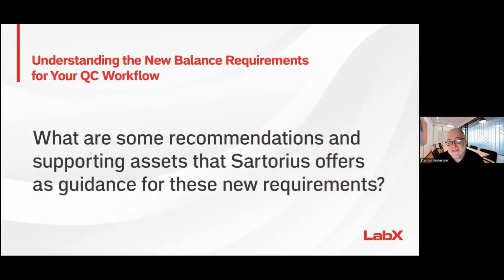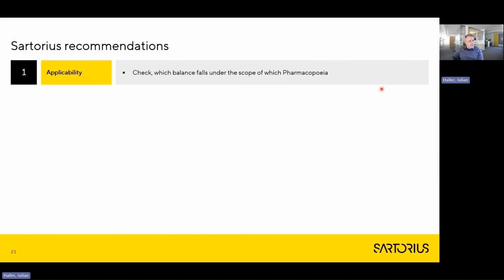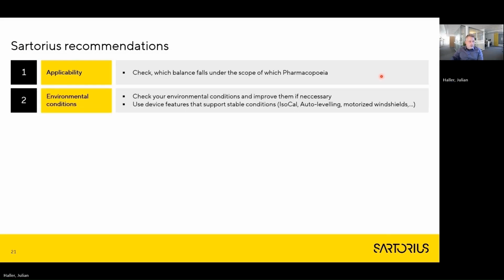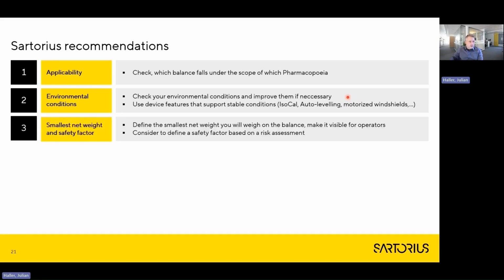What are some recommendations and supporting assets that Sartorius offers as guidance for these new requirements? Concerning the applicability, we recommend to firstly check which balance falls under the scope of which pharmacopoeia. We recommend to check the environmental conditions and improve them if necessary, and our service or application specialists will be happy to support you with these considerations. If your device has features that support stable conditions like isocal, auto-leveling, and motorized windshields, we recommend, of course, to use these features.